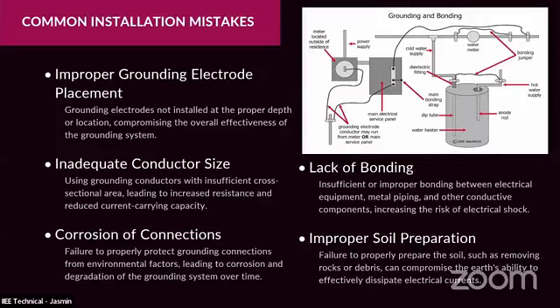Corrosion connection and inadequate conductor size - we ensure the conductor size is properly considered. Using grounding conductors with insufficient cross-sectional area leads to increased resistance and reduced current carrying capacity whenever we have faults.